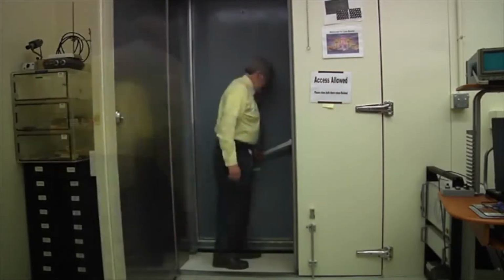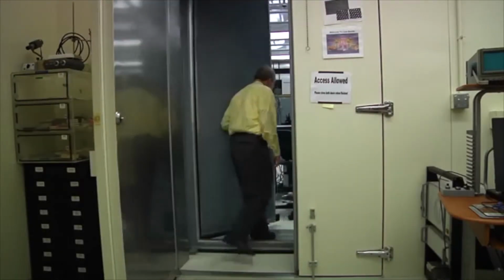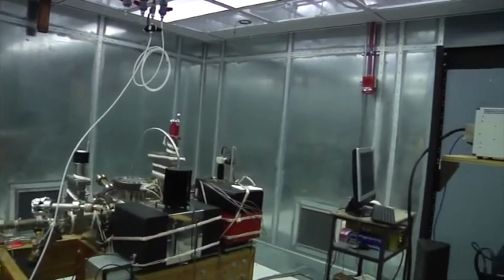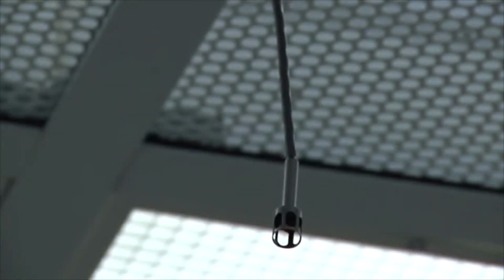For temperature control, we have a totally separate air handling system just for that laboratory. It feeds into a room with two thicknesses of wall at R45 insulation, like a commercial freezer, with a 12-inch air gap between the walls, giving extremely good insulation. With a carefully tuned control system, we're able to control temperatures to 0.01 degrees centigrade, very precise temperature control.